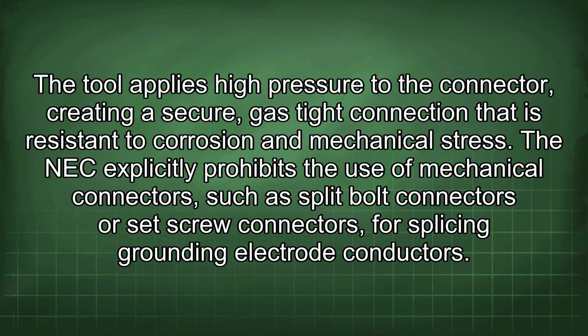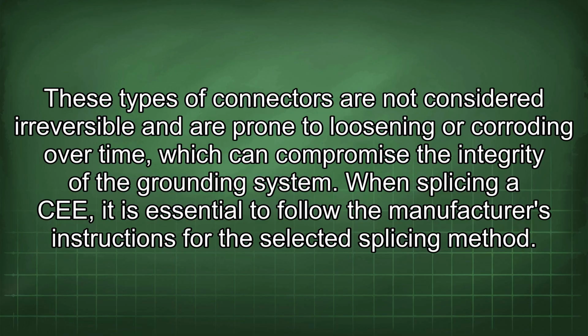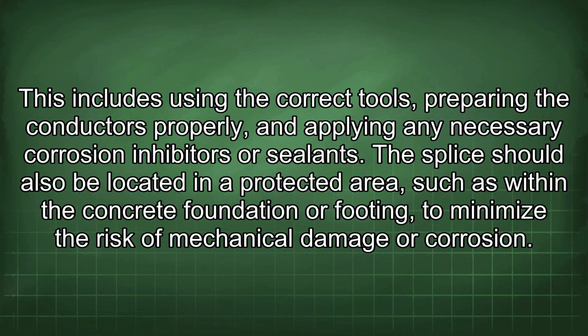stress. The NEC explicitly prohibits the use of mechanical connectors, such as split bolt connectors or set screw connectors, for splicing grounding electrode conductors. These types of connectors are not considered irreversible and are prone to loosening or corroding over time, which can compromise the integrity of the grounding system. When splicing a CEE, it is essential to follow the manufacturer's instructions for the selected splicing method. This includes using the correct tools, preparing the conductors properly, and applying any necessary corrosion inhibitors or sealants.